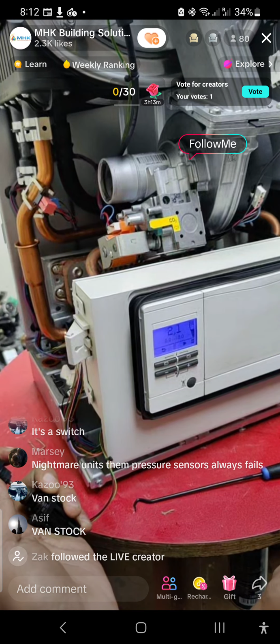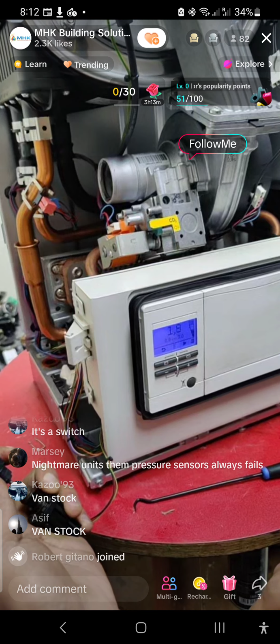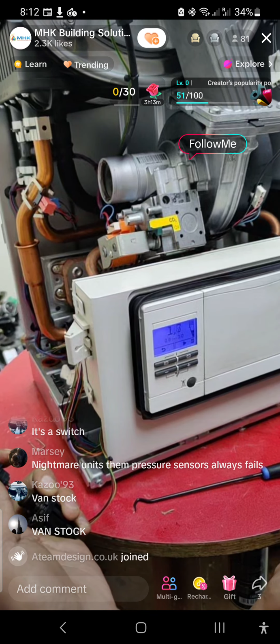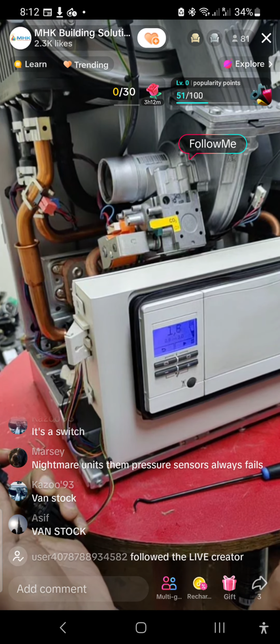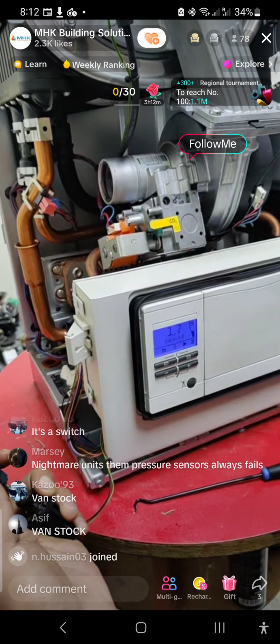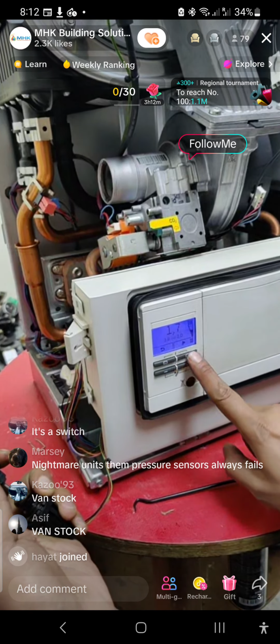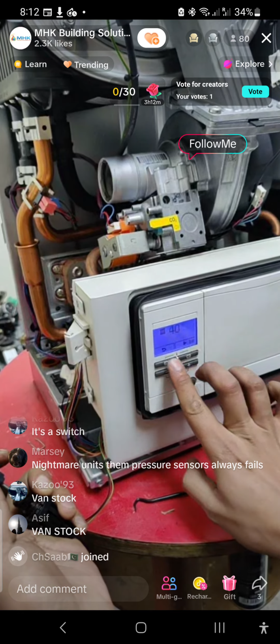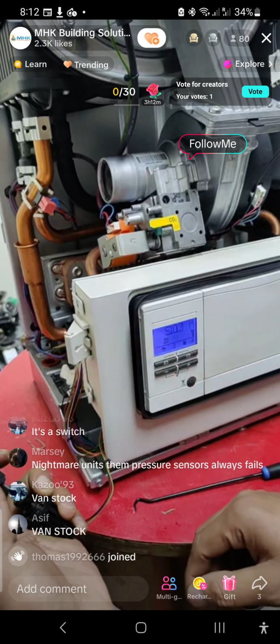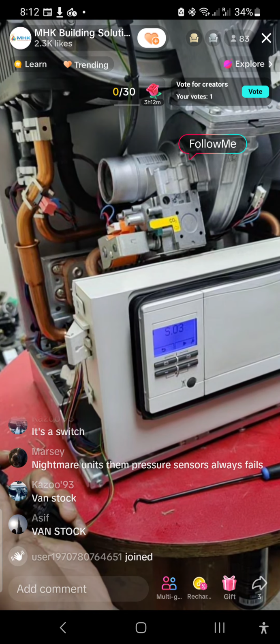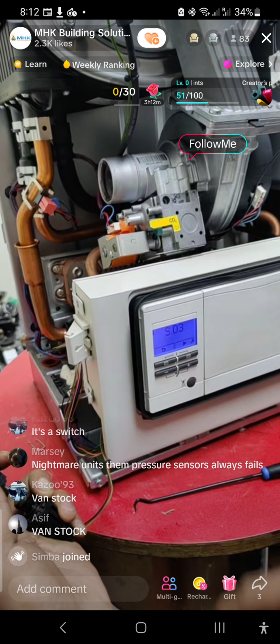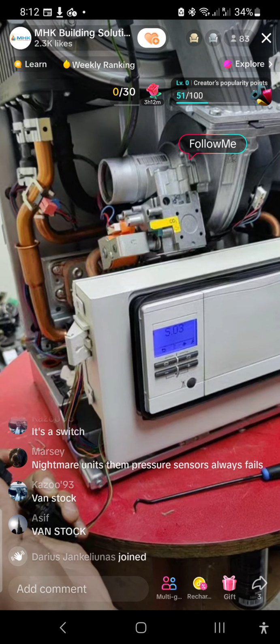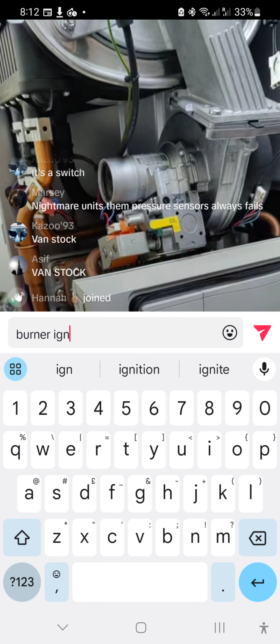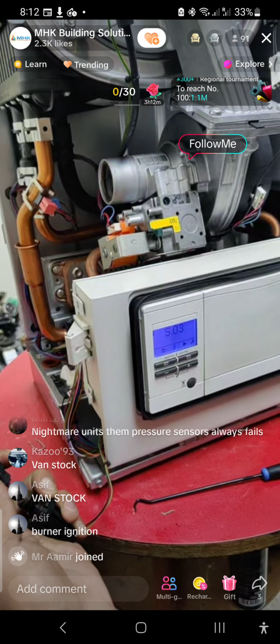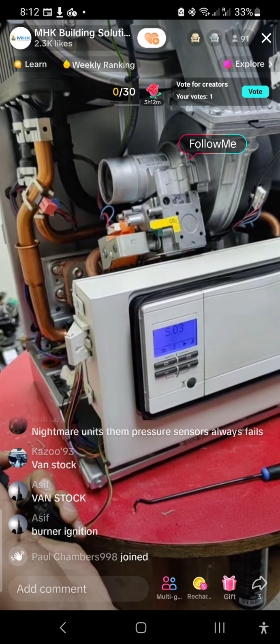I think I'm going to take some pressure out - 1.9, 1.6, 1.7. The boiler's going through a self-test as we speak. If we press these two buttons, the boiler should tell us what it's checking, what sequence it's going through. S03, I believe, is the ignition sequence. So the boiler currently is going through a self-test mode.